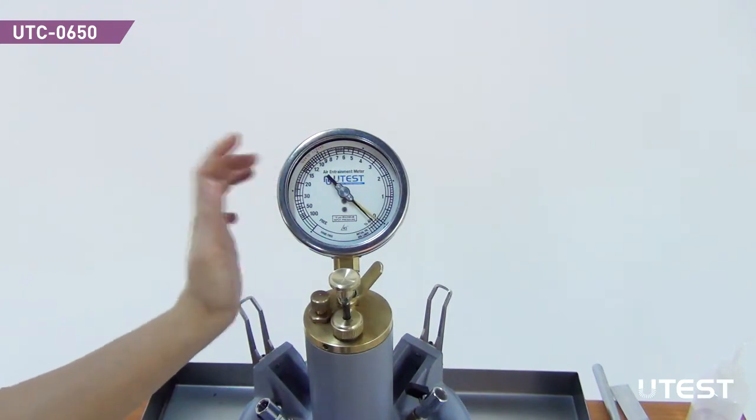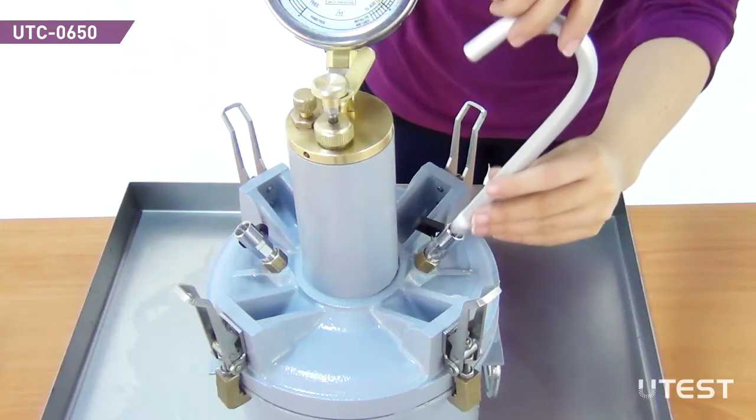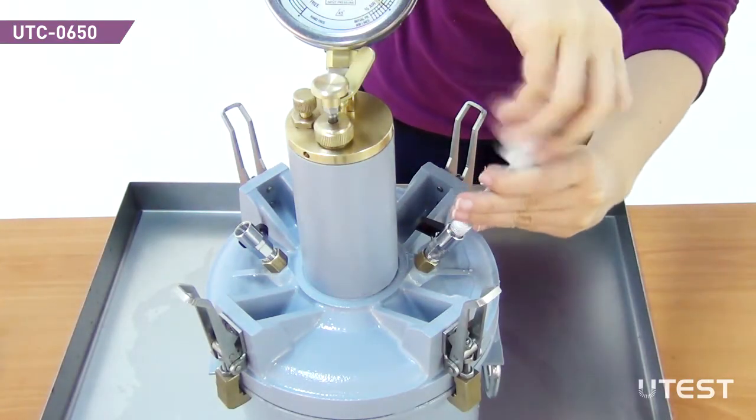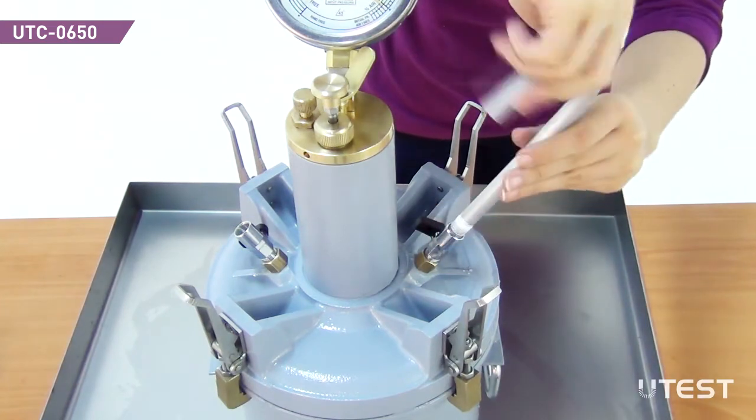Tap the gauge lightly to help stabilize the gauge hand. Screw the J-tube into the same petcock which has the inner extension tube.